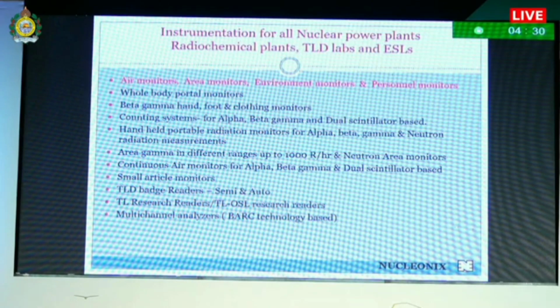For any nuclear facility or radiological facility, there are air monitors, area monitoring, environment monitoring, and personal monitoring. These are the four things that are required. These comprise various instruments: whole body portal monitors, beta gamma monitors, counting systems for alpha, beta, gamma, and dual scintillator based, handheld portables for alpha, beta, and neutron radiation measurements, area gamma monitors in different ranges, type tested and seismic qualified ones, continuous air monitors for alpha, beta, and dual scintillator based, small article monitors, TLD badge readers, TL OSL, and multi-channel analyzers, etc. These are the products which we supplied over the years to various facilities.